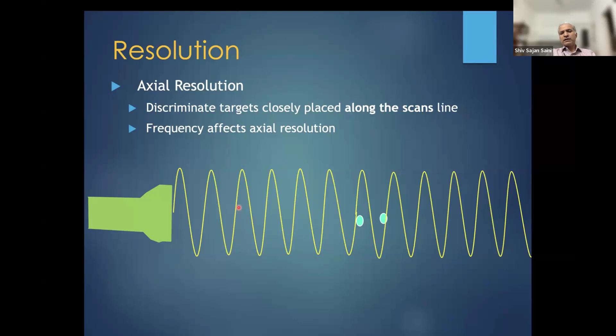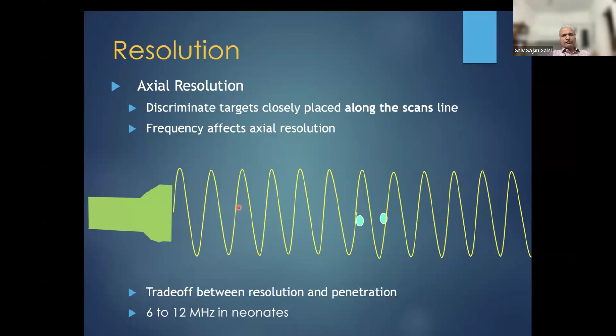Okay. So there is a trade-off between resolution and penetration. I have discussed it. If we use a very high frequency probe, then we will be unable to interrogate the deeper structures, which we have already discussed. What about lateral resolution? The lateral resolution is the ability of the machine to identify two structures which are perpendicular to the line of the ultrasound beam.